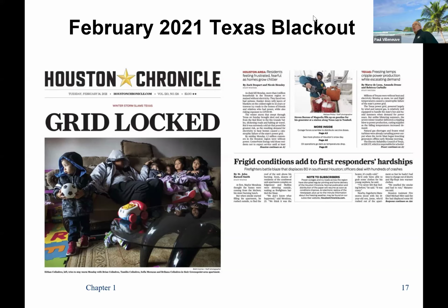And what ended up happening is ERCOT, which manages the grid there, said we have to actually turn customers off. There wasn't a fault; nothing got damaged that caused it. There just wasn't enough generation. And because you have to have that spinning reserve, that spare capacity in the event something does happen, you could have maybe 10, 20% additional generation, but a lot of customers were without power for extended periods of time. This has happened in California a lot, but it's different there. They're better about it now, but they'll either do brownouts, which means they drop the voltage specifically to a lower level.